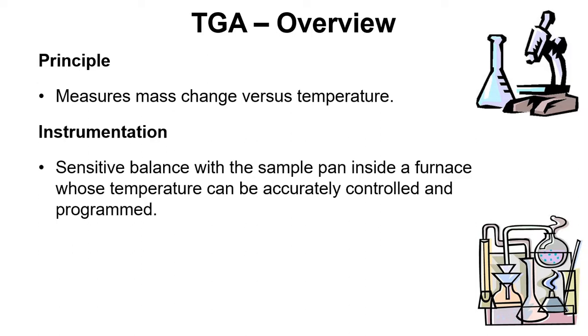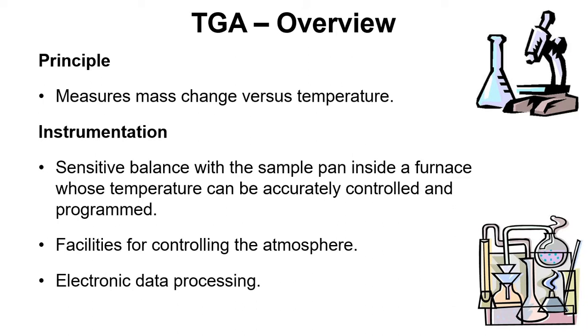The instrumentation requires a sensitive balance with a sample pan inside a furnace, and we need to be able to control the temperature of the furnace accurately and program the temperature profile. We have facilities for controlling the atmosphere around the sample and electronic data processing so we can read the information into a computer.